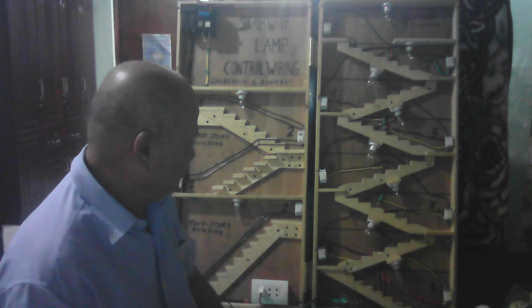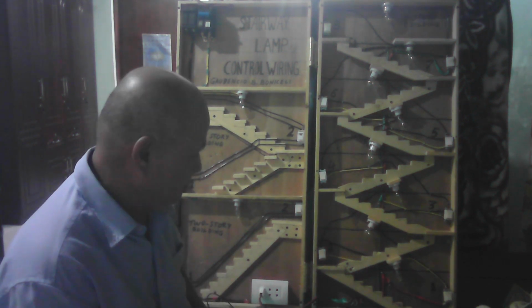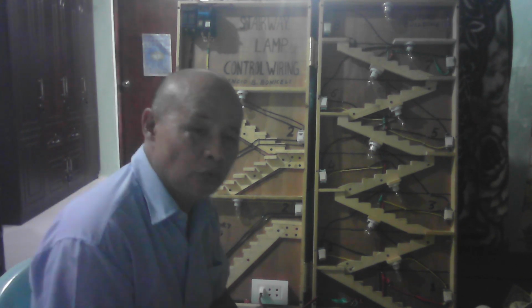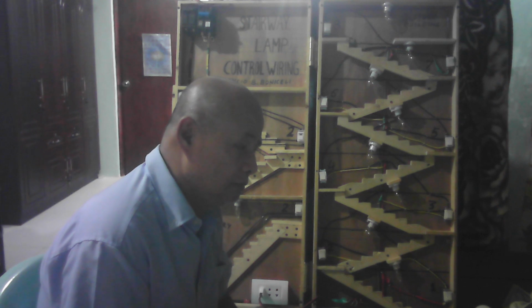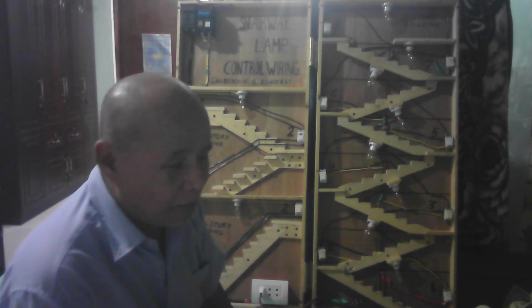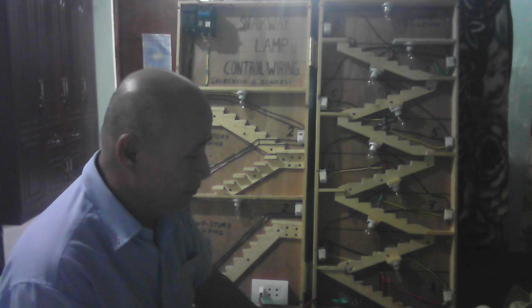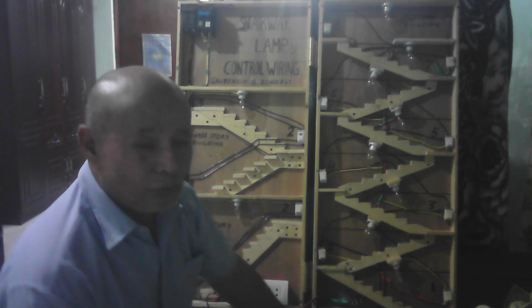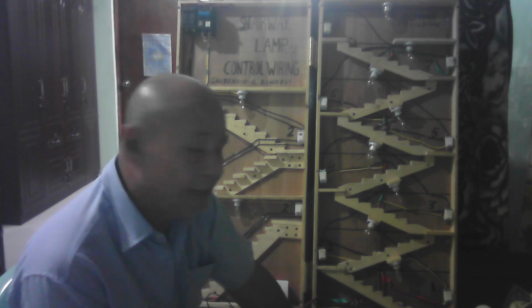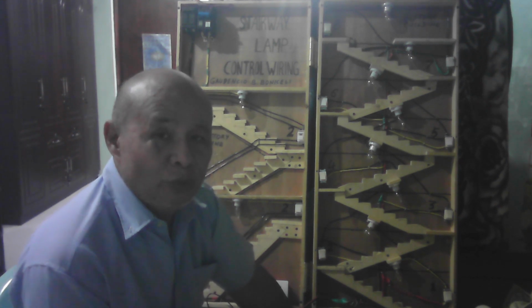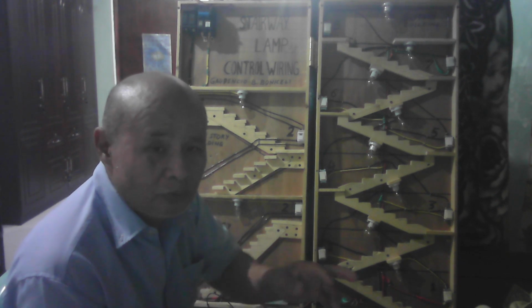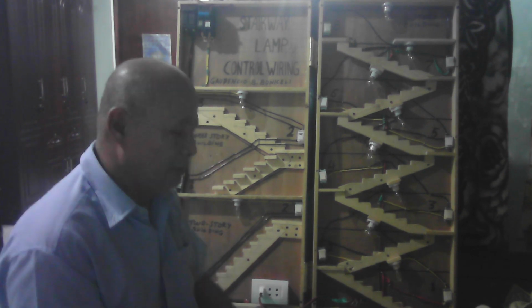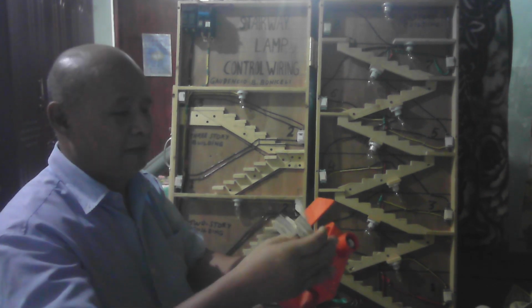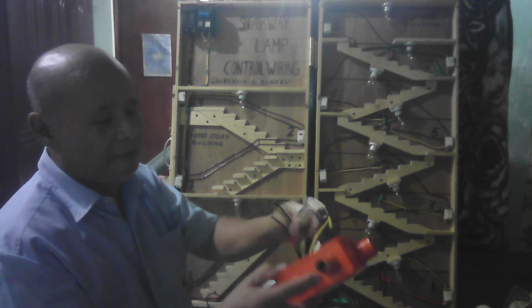And in case you are about to do some wiring for your new building, I recommend using color-coded electrical wire. If there is no available color-coded electrical wire, only black, it's quite difficult to do the installation, or especially the troubleshooting or repair. It's difficult to determine which one is for the main line, line 1, line 2, or the common line, traveler, and ground line. Like this, no? If this is all black, it's difficult.